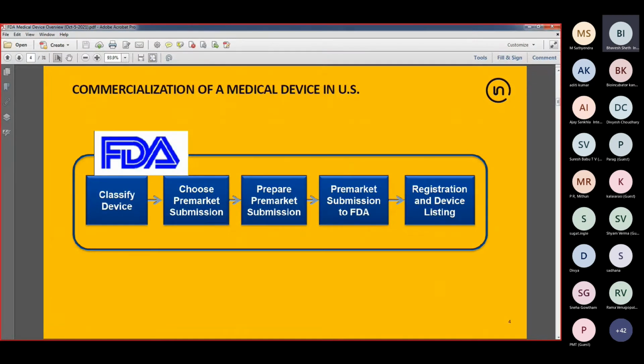But before I get into more about device classification, I just want to highlight the 5 most important steps for bringing a medical device in US, for marketing a medical device in US. Obviously, classification of the device is of utmost importance. You start there. Depending on the classification, you may be required to submit a pre-market notification, a regulatory submission to the FDA to gain permission to market the device. We'll look into that a bit later in the presentation.